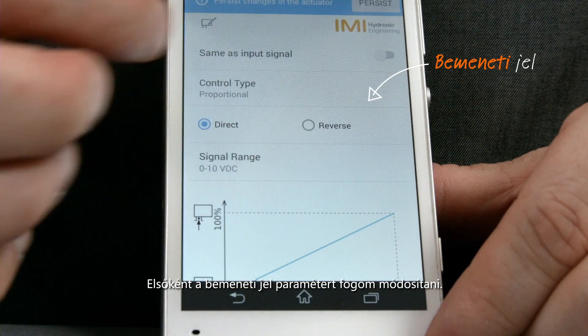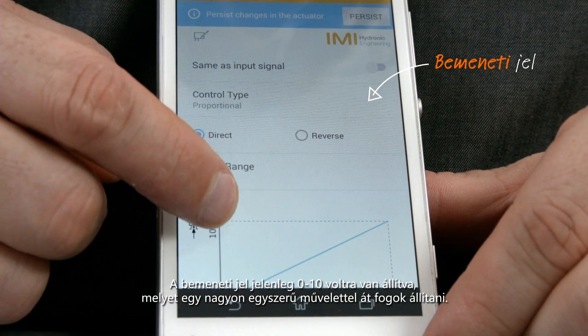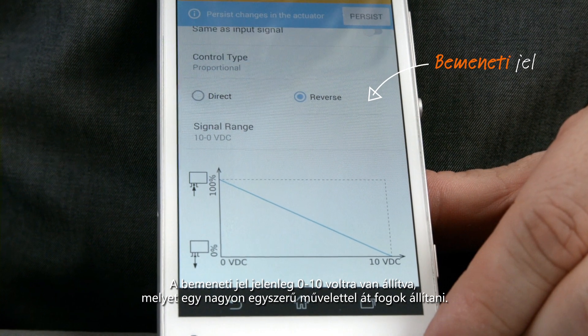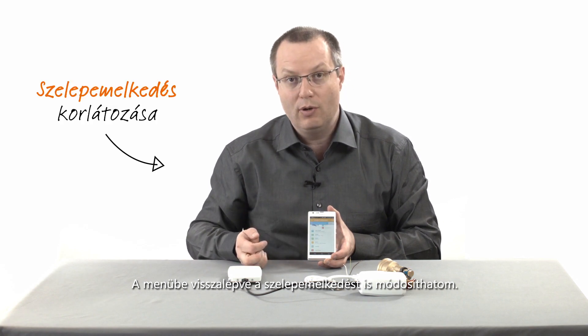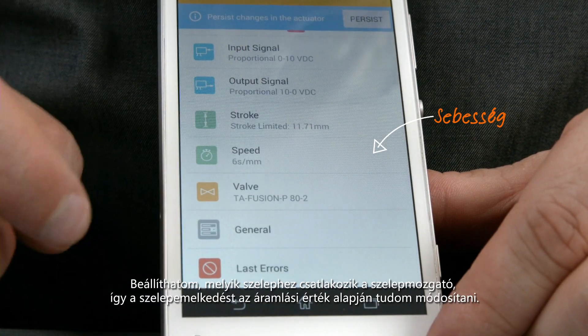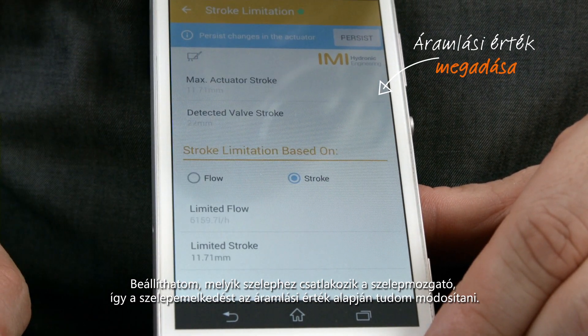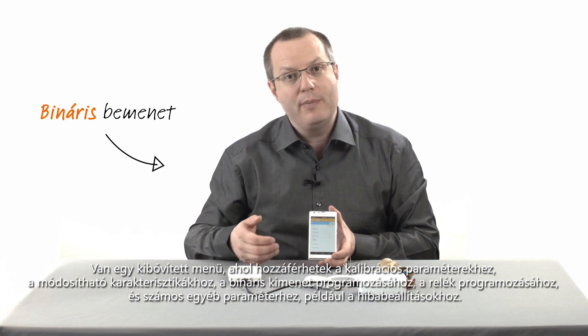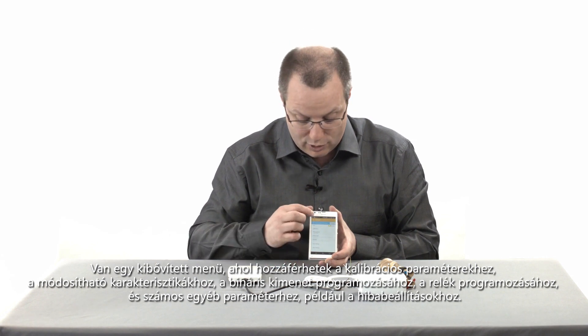The first parameter I'm going to change is for instance the input signal, which is currently set to 0 to 10 volts, and I am going to reverse it in a very simple way. Getting back to the menu I also get access to the possibility to change the stroke, I can choose the speed, I can set up the valve to which the actuator is connected, which allows me to then adjust the stroke through a flow value. In the extended menu I get access to calibration parameters, characteristics that can be adjusted, programming of binary input, programming of the relays, and a lot of other settings like error settings.